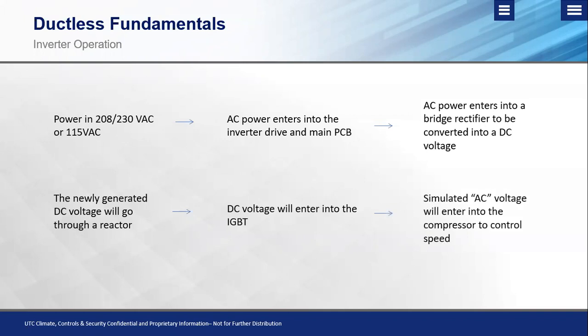Okay, now what we're going to look at that as is a simulated AC voltage. Now, when we say simulated, a lot of guys will ask, what does that mean? What we're doing is we're essentially mimicking an AC sine wave by pulsing DC voltage to the compressor. So if you want to look at it from a basic overview, we're essentially fooling the compressor through a sine wave. Since the compressor doesn't really know the difference between AC or DC voltage, what it does know is the sine wave. And by pulsing DC voltage, we can mimic an AC sine wave, which in turn can control the speed of the compressor.